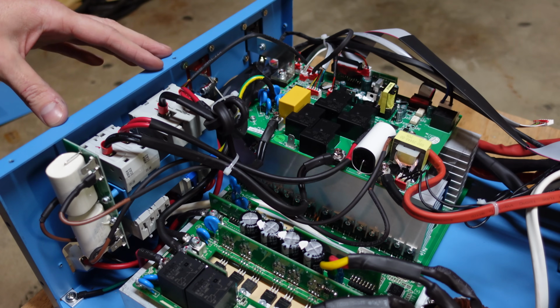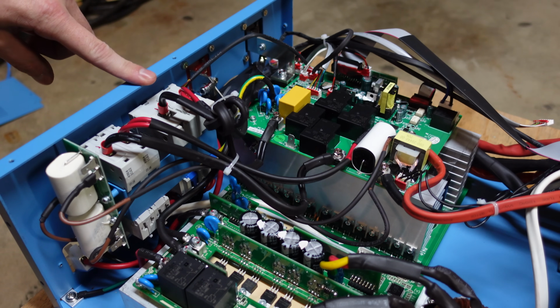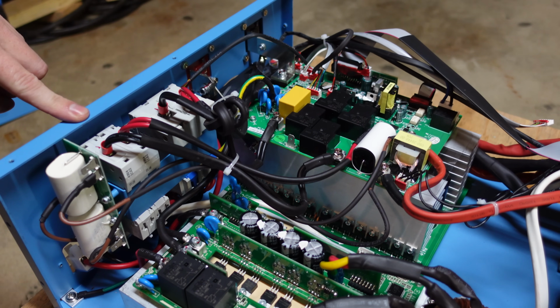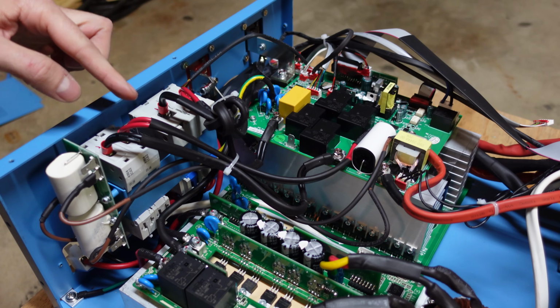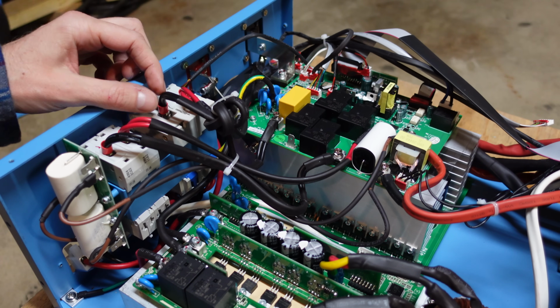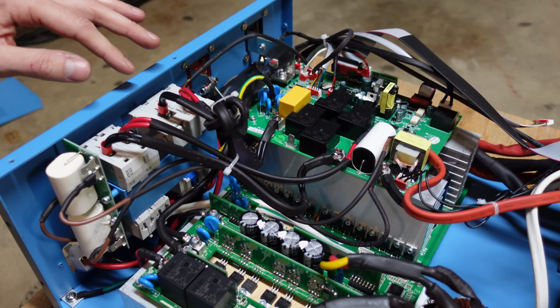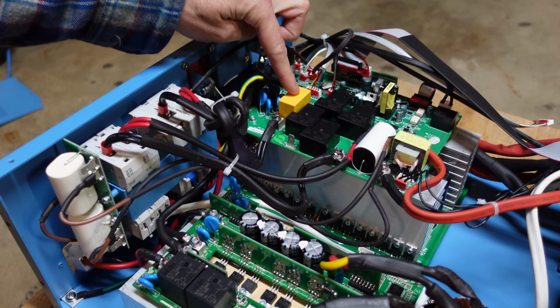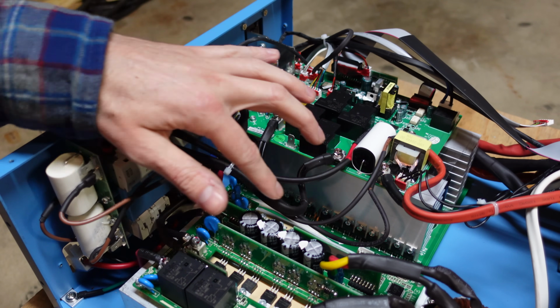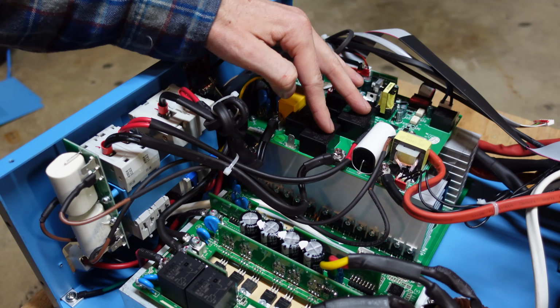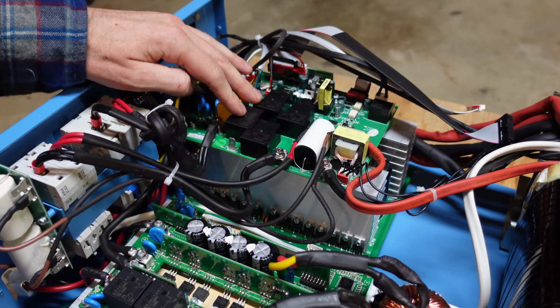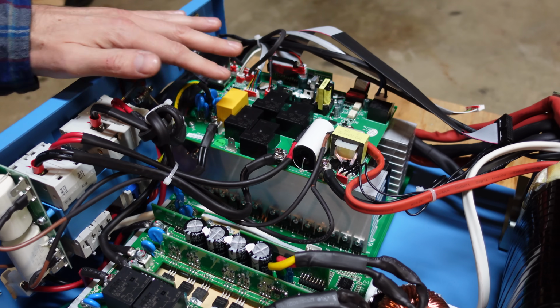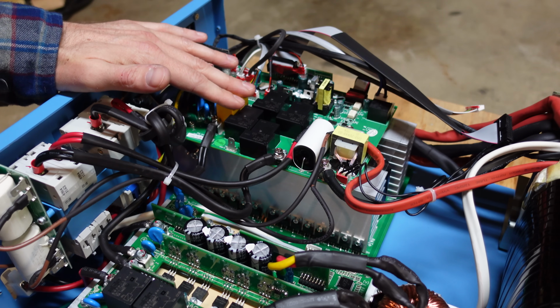So looking at the AC portion of this, we have our input AC breaker and our output AC breaker. And all 4 of these connections are a pair of 12 gauge AWM rated wiring. The input breaker goes directly into this top circuit board, and the output leads are going to, well, the opposing side of the same circuit board. So over here we have a set of 4 relays. This inverter does have an internal built-in transfer switch.